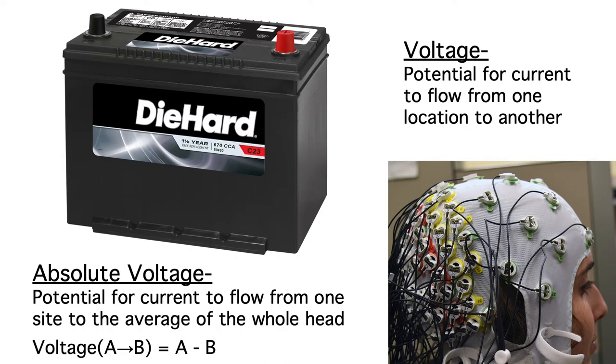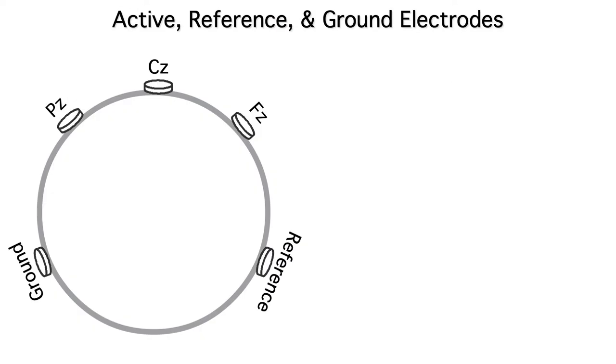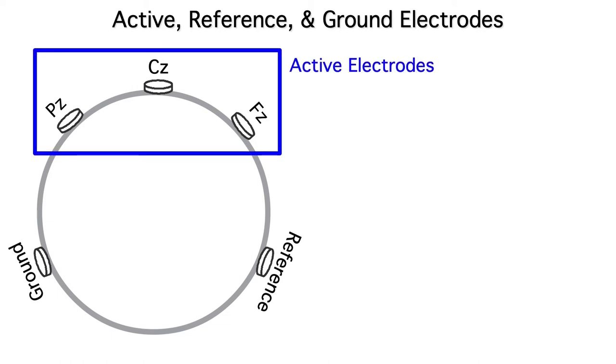Now let's talk about how the EEG is actually recorded. To get one channel of EEG, you actually need three electrodes: active, reference, and ground. For example, imagine that we wanted to record from FZ, CZ, and PZ. These would be our active electrodes.